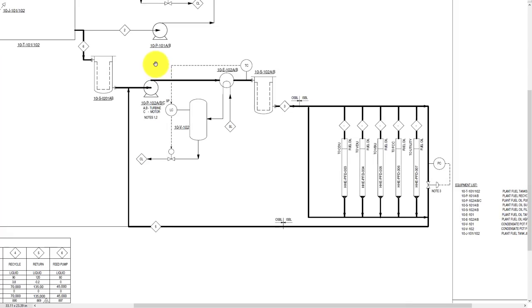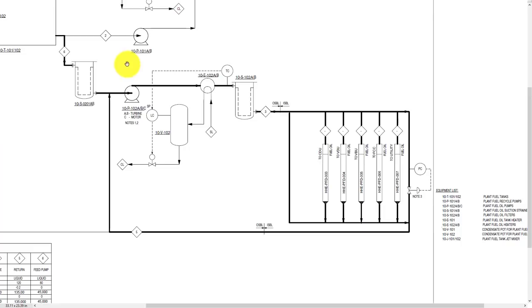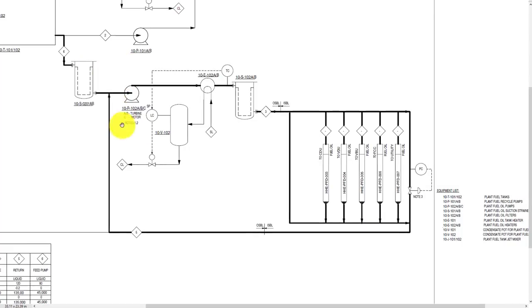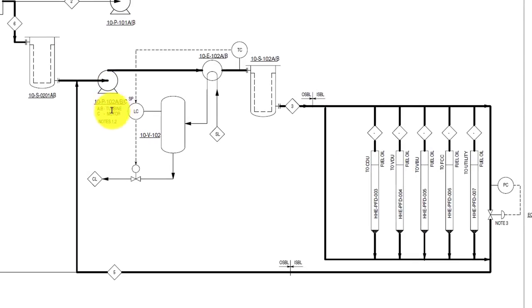Let me adjust the PFD on the screen so that we can conclude our video. Oh, these pumps are turbine driven. That means these are critical pumps. Normally, turbine driven pumps are provided where you want to run the pump even if there is a total power failure in your plant.